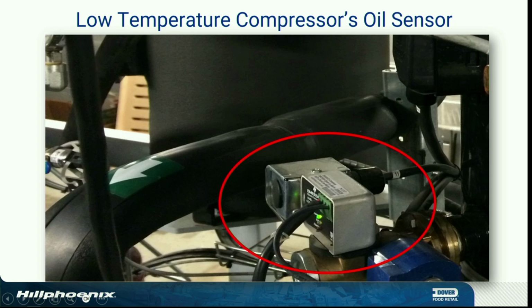But it'll also trip and you'll get a red light. That red light will come on. The compressor shuts off, it goes down into cool down mode. It will restart again and it'll try 5 times. Then it locks out. When that red light's blinking red, it's locked out. The only way to reset it is to cycle the power. Okay? If you locked out, I would start looking at my oil system, especially those inline filters. Something's wrong. But it's not going to be just low temp. It's going to be all 4 compressors on that rack because they're all off of one oil line. If in a pinch, if you don't have another inline filter, you can't get it cleaned anymore, pull that stone out and just put it in there without it. It's better to run the rack than to not run the rack, right? And get another inline filter as quick as you can.